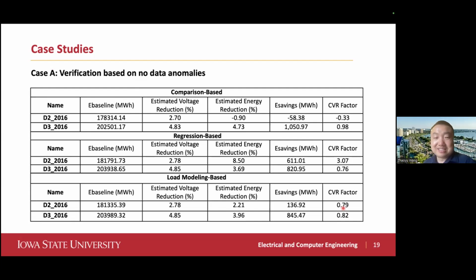So which one is correct? Honestly, it's hard to say, because you will never know what would happen if there's no voltage reduction. But one thing I can say is that negative is certainly wrong. We carefully selected the feeder, so it won't have a negative CVR factor. It's not an industrial feeder, it's a residential feeder, so it must have a positive CVR factor. Also, 3 seems very high, which isn't possible. The CVR factor should be around 1, based on our experience. So I'm not saying this is exactly correct, but I'd say it's closer to the truth.